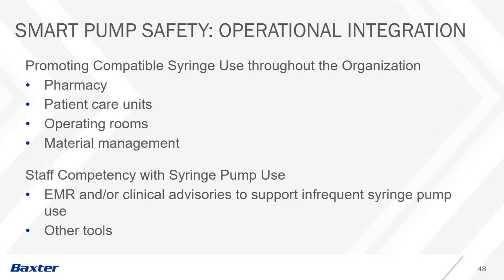We learned that good relations and clear communication with materials management is essential to establish understanding of the necessity of compatible syringe stock. Helpful functionality within the pump itself is that the compatible syringe brands and sizes are actually programmed into the pump. Therefore, the pump tells the end user if the loaded syringe is not compatible.